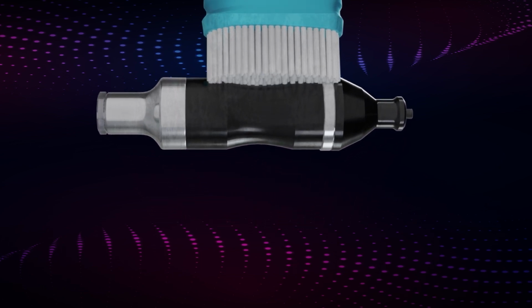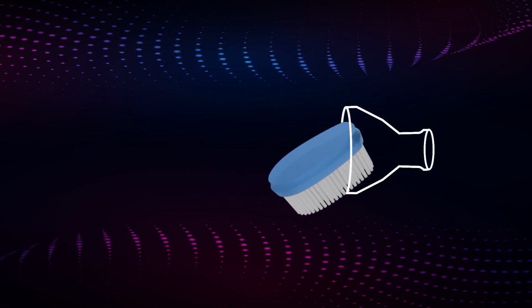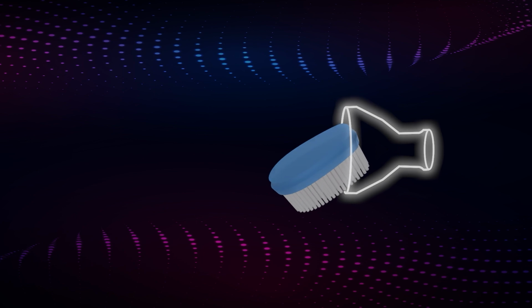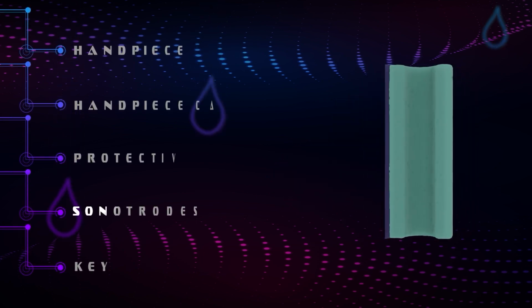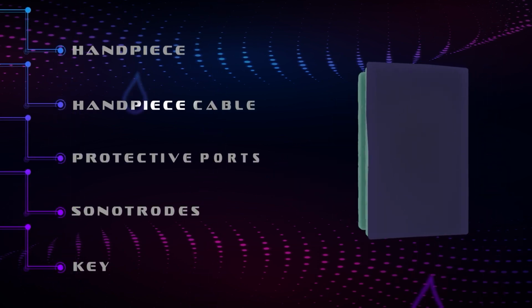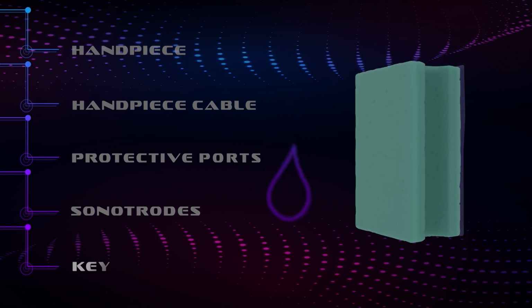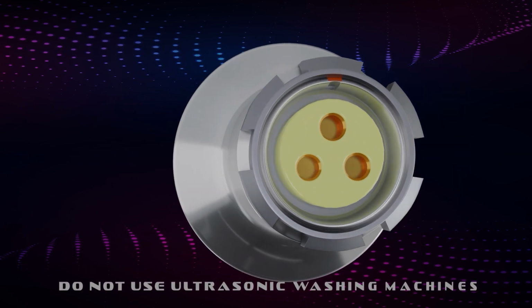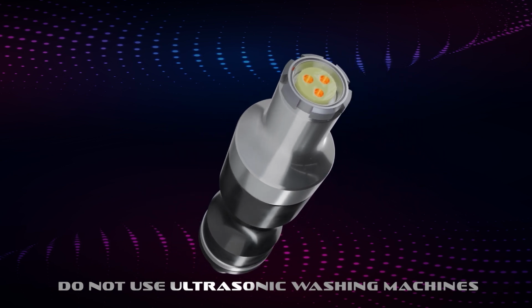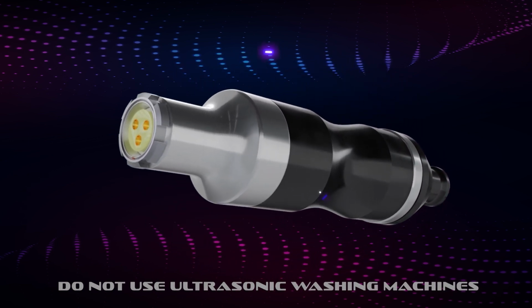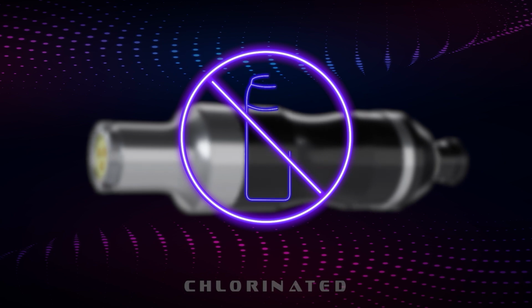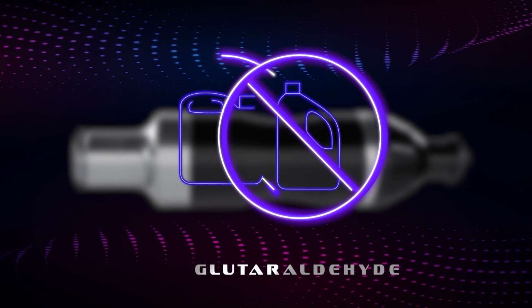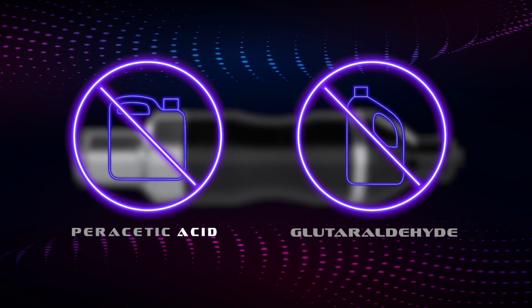Use a soft bristle brush to clean the handpiece and a specific brush for sonotrodes or equivalent to clean the inside of the handpiece nozzle. Rinse all the components with warm, clean water using a sponge or similar tool. Remember not to use ultrasonic or automatic washers to clean the handpiece. Avoid the use of chlorinated or abrasive products, as well as processes involving glutaraldehyde or liquid peracetic acid in any concentration in the handpiece cleaning.